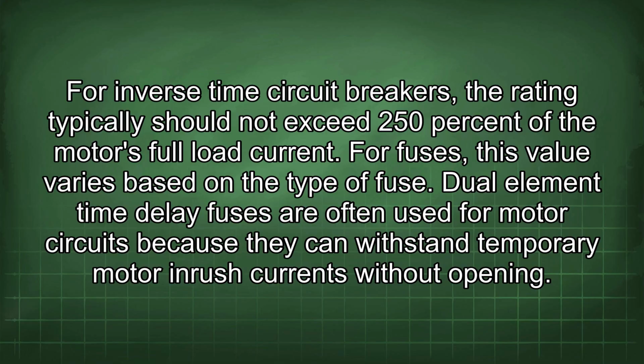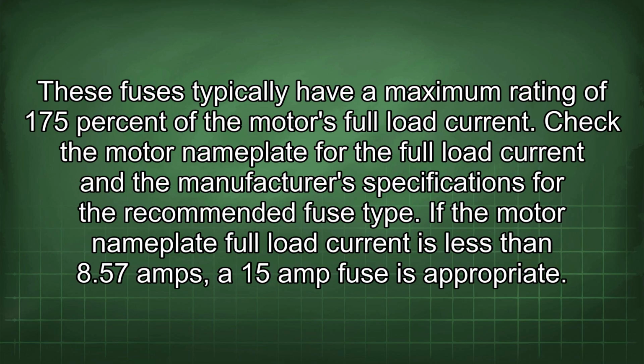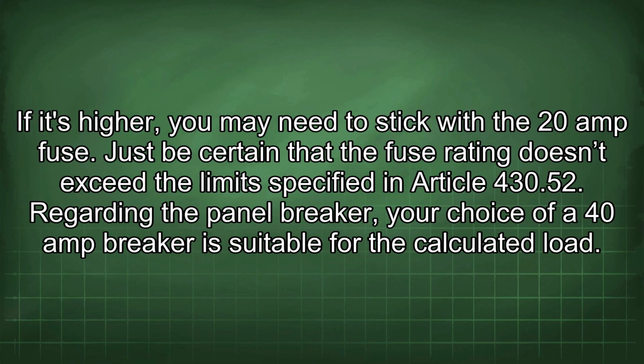Dual element time delay fuses are often used for motor circuits because they can withstand temporary motor inrush currents without opening. These fuses typically have a maximum rating of 175% of the motor's full load current. Check the motor nameplate for the full load current and the manufacturer's specifications for the recommended fuse type. If the motor nameplate full load current is less than 8.57 amps, a 15 amp fuse is appropriate. If it's higher, you may need to stick with the 20 amp fuse. Just be certain that the fuse rating doesn't exceed the limits specified in Article 430.52.